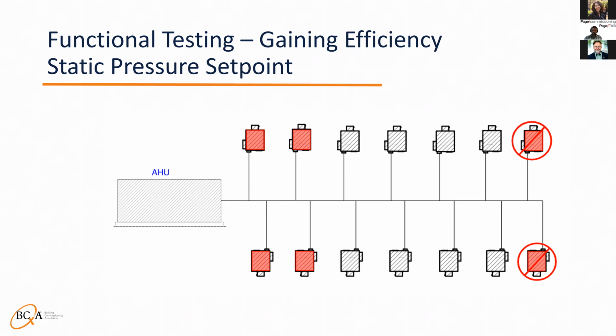At that point, you may want to check the inlet conditions to that box, see if the correction factor on the box makes sense, see if the max cooling design CFM will mean flowing over 2,000 feet per minute through the box inlet. The box may need to be increased in size. Ideally, some of these issues would have been caught during the design phase or during a site observation.